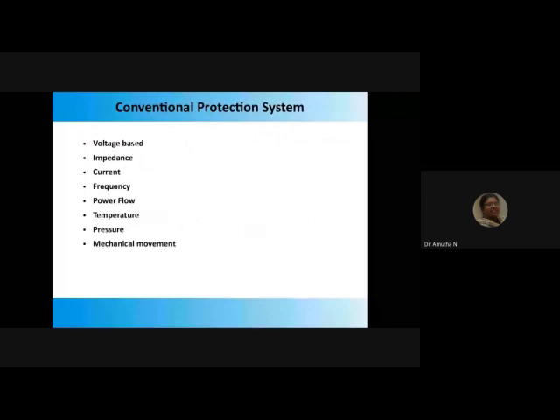So how is this conventional protection system based on these parameters? Usually the relay system depends on one parameter or one electrical value of that particular system—it can be a voltage relay (under voltage or over voltage), an over current relay, impedance relay, or frequency relay (under frequency or over frequency). If you take an over current relay, it senses only a particular value of current and then initiates the action.